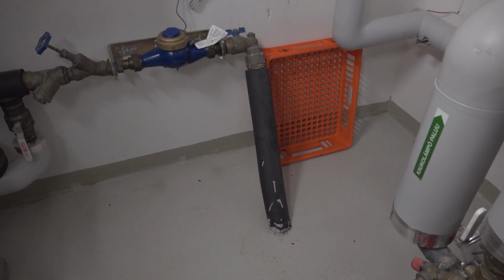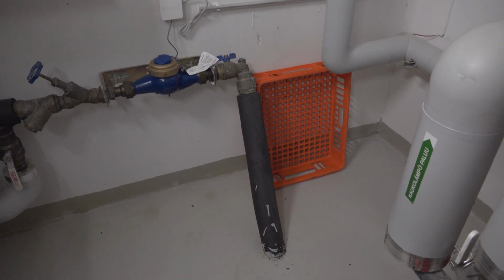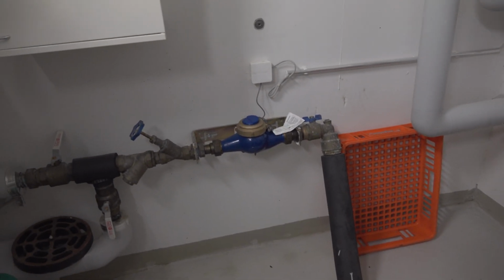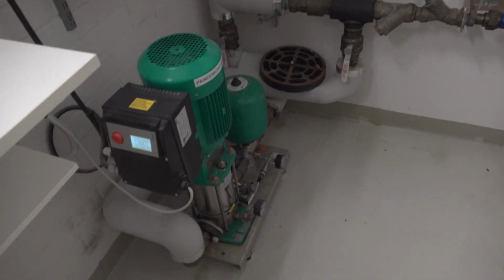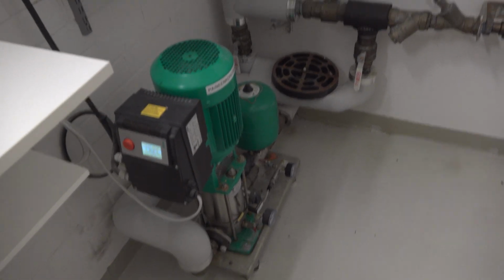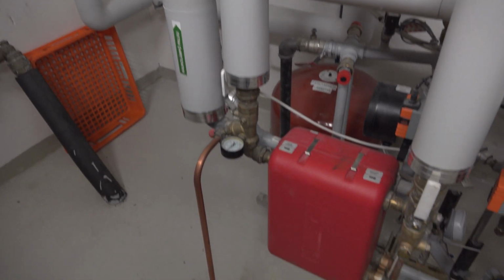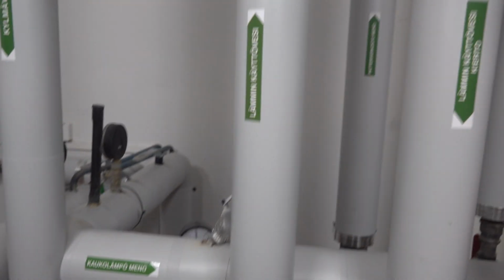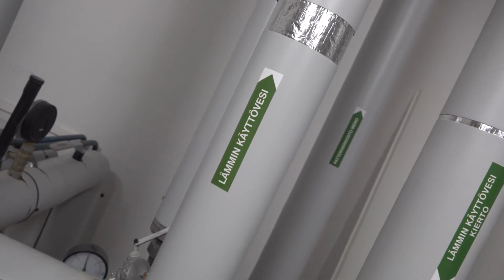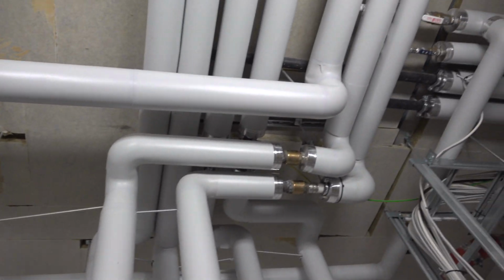This is the hole where the cold water from the city comes to our apartment building. There's a measurement there, a pump to add some more pressure if needed. And you can see it goes all the way from there to the heat exchanger here. And then it gets out as lämmin käyttövesi, as hot water to the apartments.